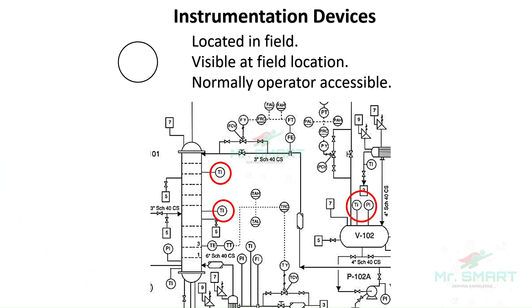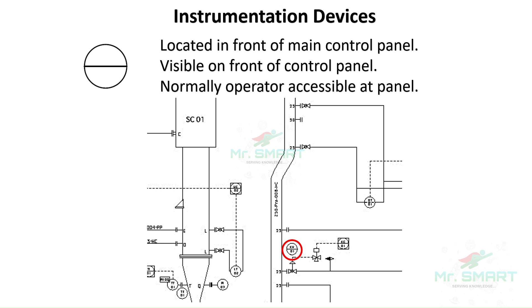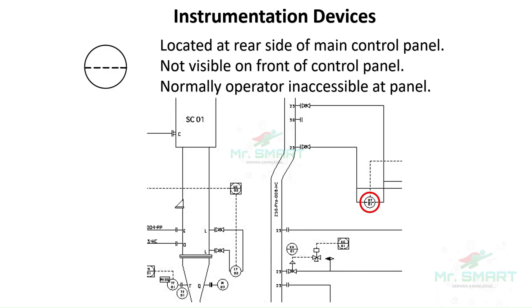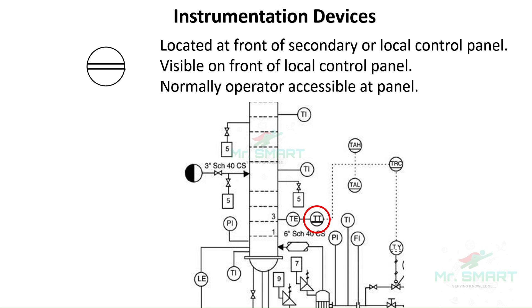The next important thing to know in P&IDs is the representation of instrumentation devices. Any instrumentation device mentioned inside a plain circle represents that the device is located in the field, visible at the field location, and can be normally accessed by the operator. Instruments mentioned inside a circle with a single horizontal continuous line represent that the device is located in the main control panel, visible only at the front side of the control panel, and can be normally accessed by the operator. Instruments mentioned inside a circle with a single horizontal dashed line represent that the device is located at the back side of the main control panel, not visible at the front side, and cannot be accessed by the operator normally. Instruments mentioned inside a circle with double horizontal continuous line represent that the device is located in the secondary or local control panel and can be normally accessed by the operator.